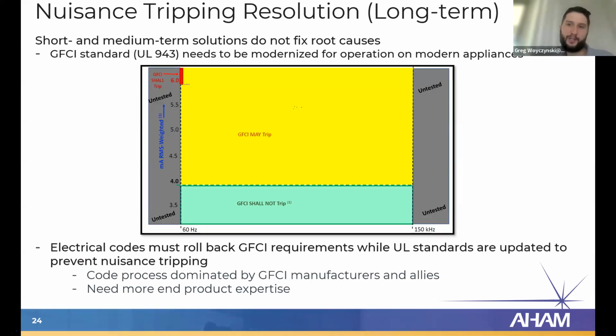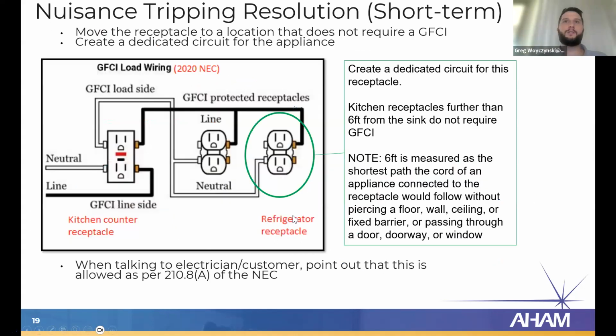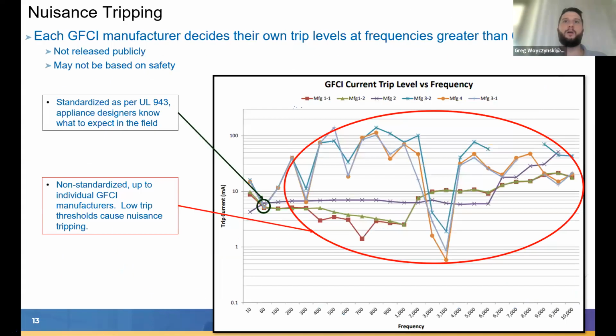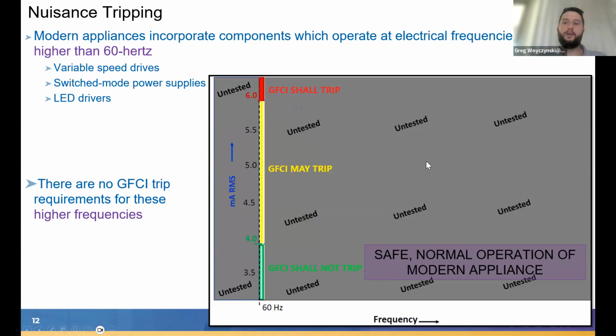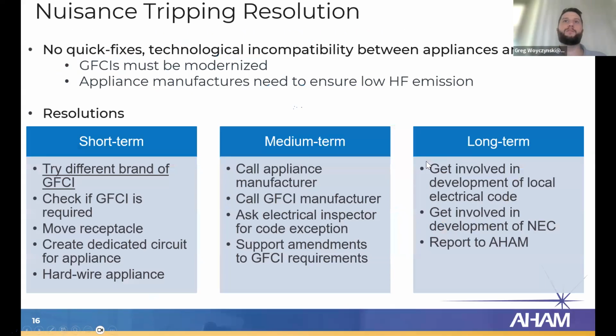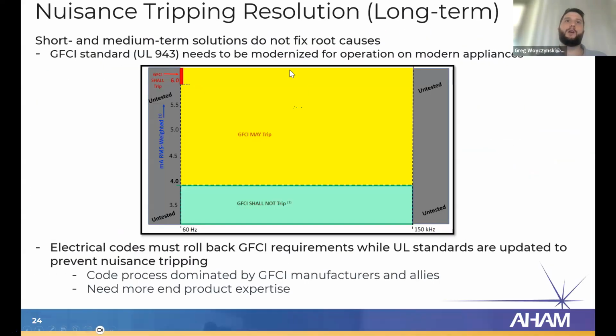The long-term resolution. This doesn't totally pertain to your everyday work, but it is something you should be aware of. They are working on updating the requirements in the UL standard, UL 943. So rather than all this gray area that we saw here, we want to better define those requirements for high frequencies. This is the solution for updated GFCI specifications.